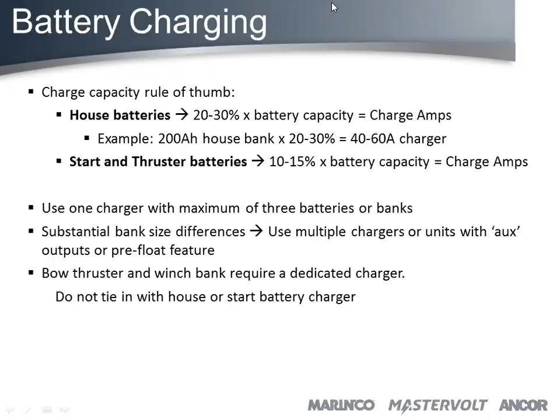If there's a substantial size difference between the banks, use a charger with the big output and the 2 auxiliary outputs, or use 2 separate battery chargers, one for house and one for the starting batteries. Another option moving forward would be using chargers with the pre-float application. Bow thrusters and winches, I see it all the time, they're tying them into the house battery charger. The house battery charger typically sits pretty far from that winch or thruster bank. Always use a separate dedicated charger for that. Don't tie it into one of the outputs of the main bank. Any questions about chargers?